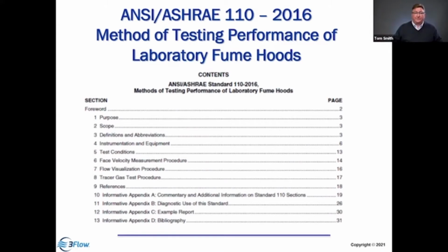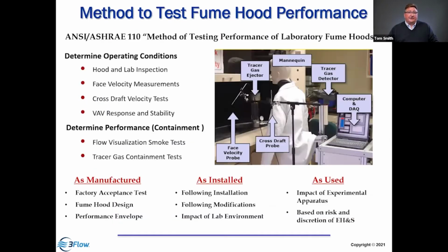Okay, perfect. All right, so the ASHRAE 110 test was written originally in 1985. It was updated in 1995, and then most recently again in 2016, and it's currently under revision right now. And so it covers a variety of different methods, from measuring face velocity to conducting smoke visualization tests and conducting the tracer gas test. And we're going to go through this standard in more detail, but first we need to look at how it is employed.